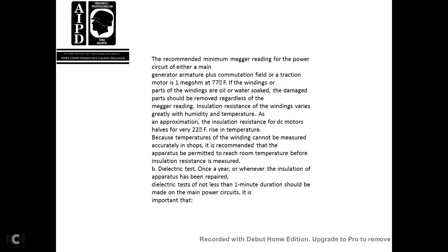The recommended minimum megger reading for the power circuit of either the main generator or the apparatus, plus the commutating field of the traction motor, is 1 megohm at 75 degrees Fahrenheit. If part of the windings are oil and water soaked, the damaged parts should be removed, regardless of the megger reading. Insulation resistance of the windings varies greatly with humidity and temperature. As an approximation, insulation resistance of DC motors halves for every 25 degrees Fahrenheit rise in temperature, because the temperature of the winding cannot be measured accurately in the shops. It is recommended that the apparatus be permitted to reach room temperature before insulation resistance is measured.